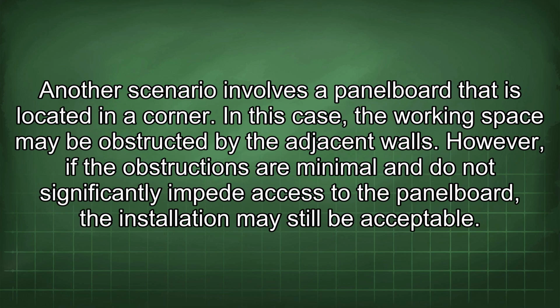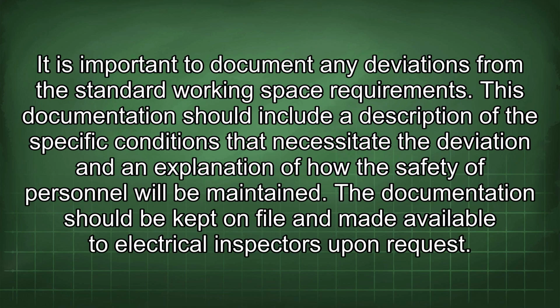Another scenario involves a panel board that is located in a corner. In this case, the working space may be obstructed by the adjacent walls. However, if the obstructions are minimal and do not significantly impede access to the panel board, the installation may still be acceptable. It is important to document any deviations from the standard working space requirements.